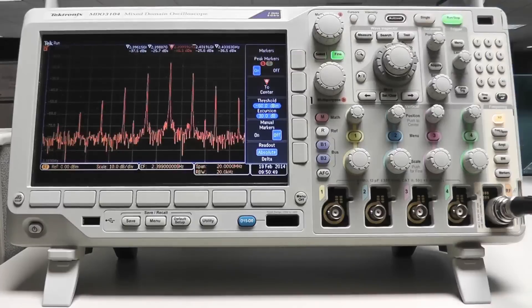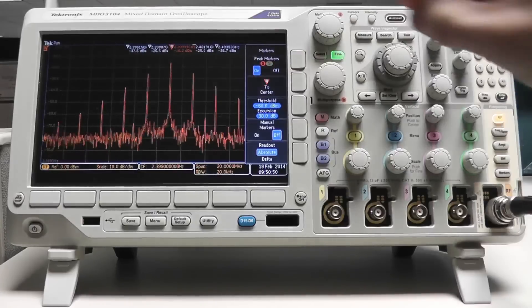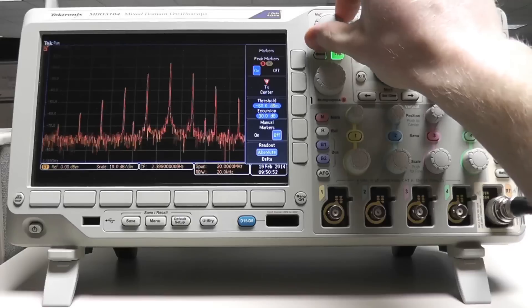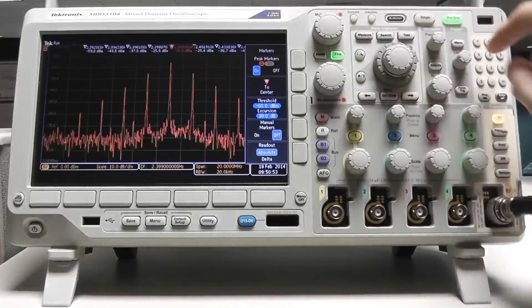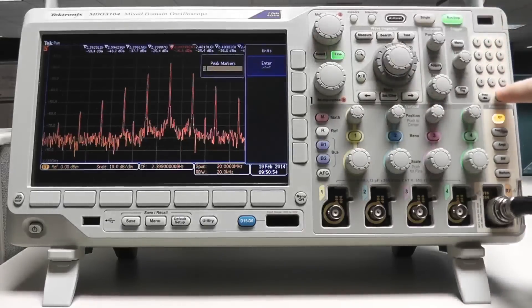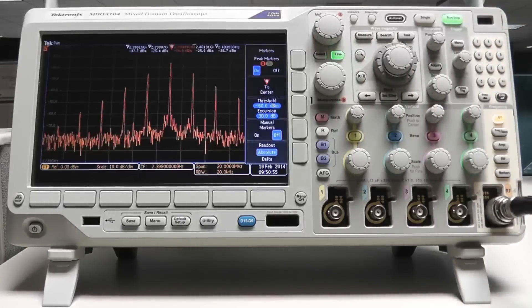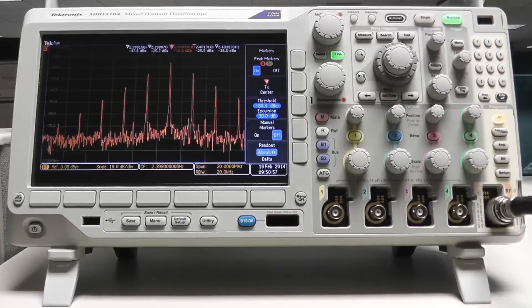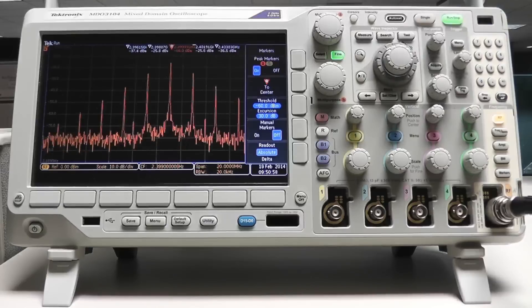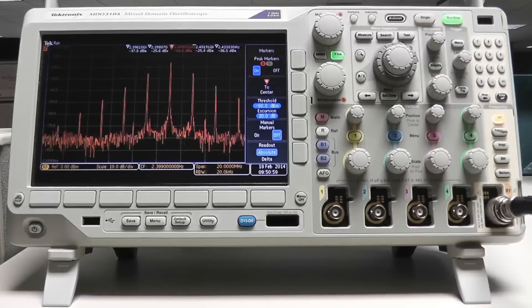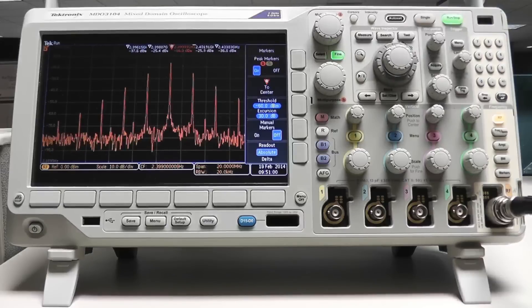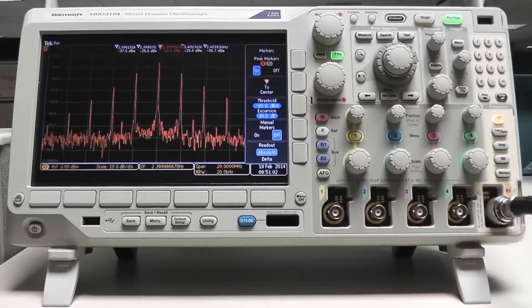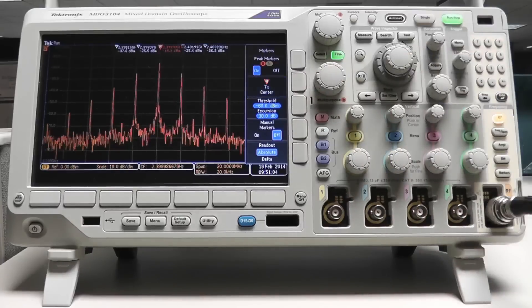You can also use the multi-purpose knob A or the keypad to change the number of markers. If you weren't quite right on the center frequency, you can move the center frequency of the spectrum analyzer to the frequency of the reference marker by pressing the R to center button.